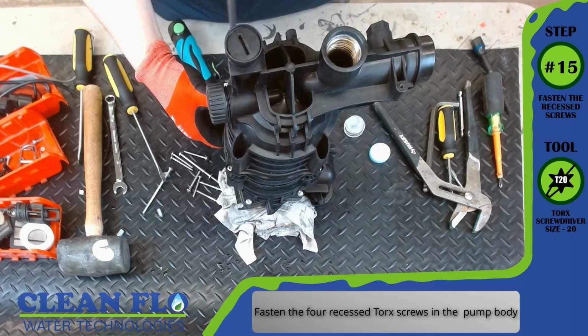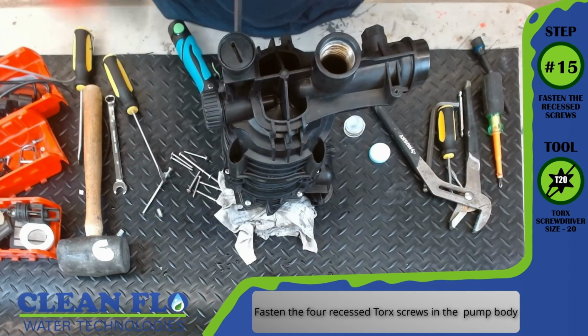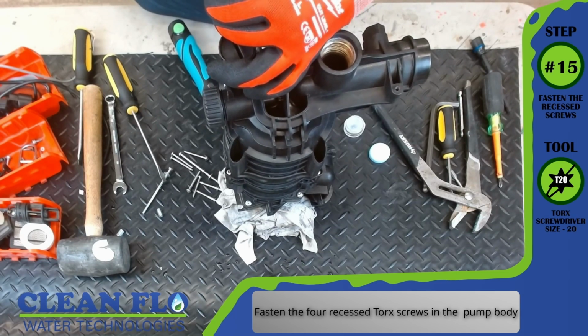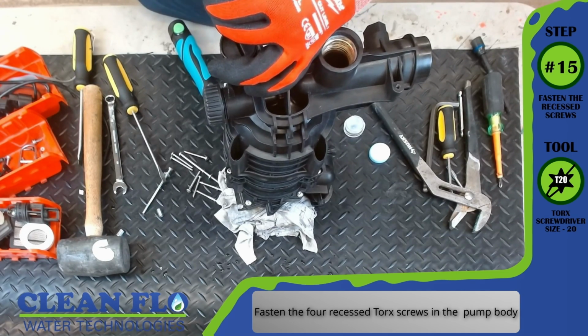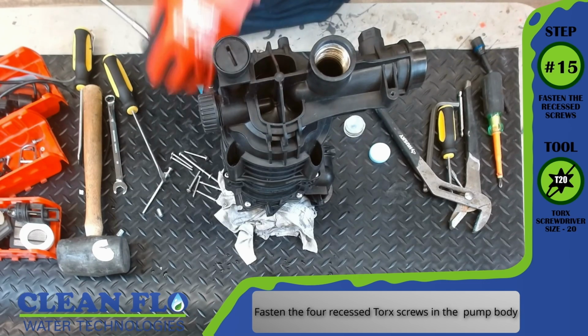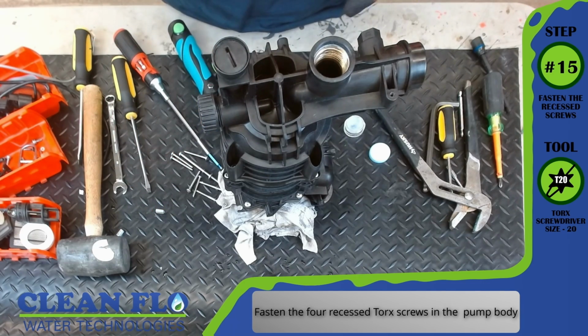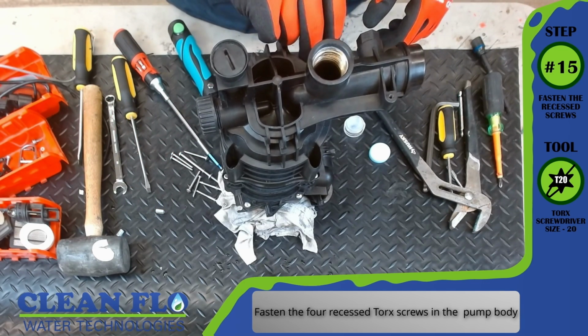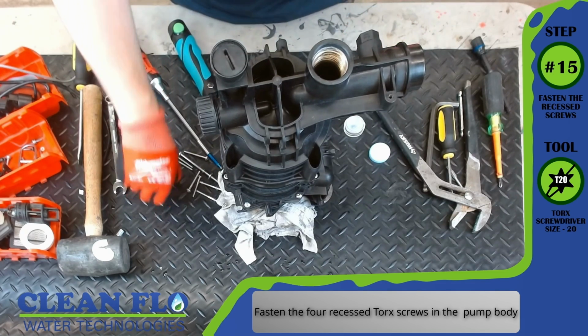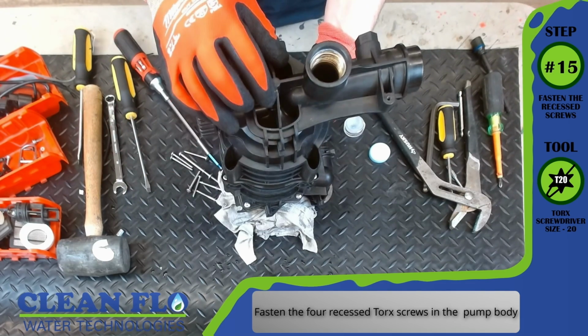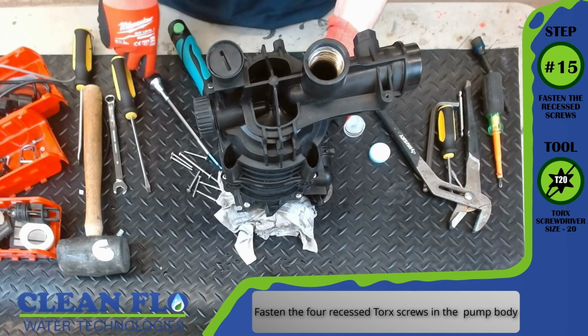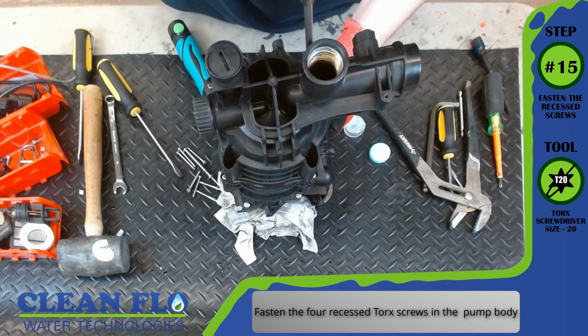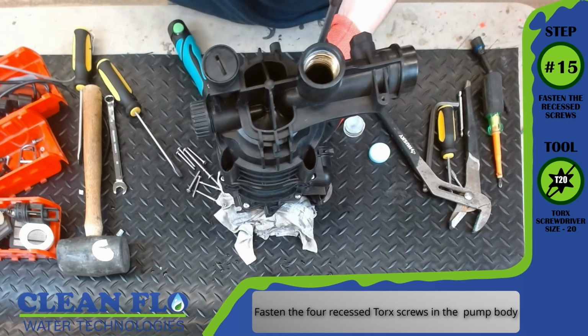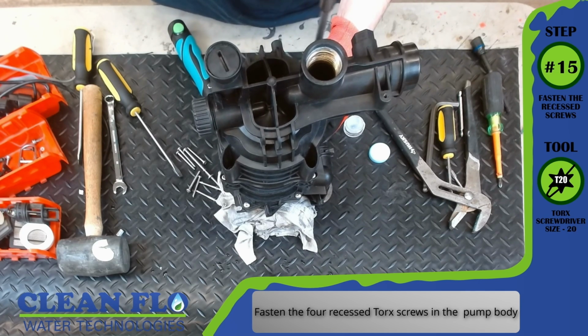Because this requires a little extra force, we typically do this stage by hand and use our hand to tighten the screw. And as soon as we start to see the pump body slide down over the O-ring, we move on to the next screw. The slower and the more steady you take this stage, the more successful you'll be in creating a complete seal on both the O-rings. Do not rush this step.